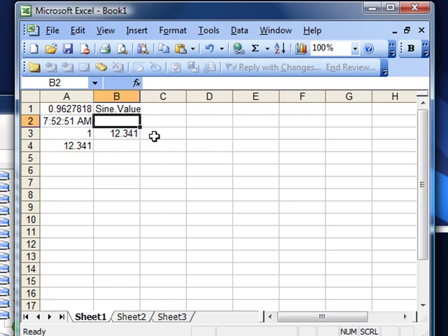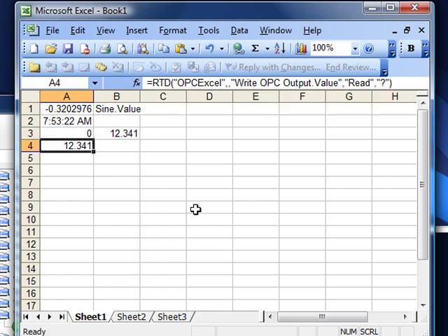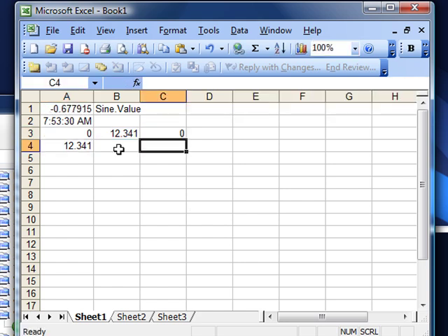So you can see the formulas are very adaptable to be arguments of any cell value that you would like it to be. Back to the write function, you notice that topic 5 can be used to either disable or enable the write. So you can start off by making that a cell location. Let's make that C3 as the parameter. Whenever C3 is 0, the write will be disabled. We'll put in a value to write of a value of 10. You notice that the value isn't being written right now because the enable to write is currently set to 0.